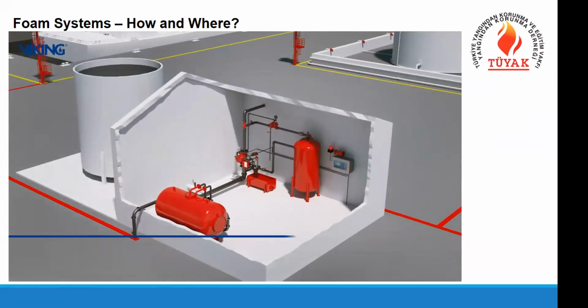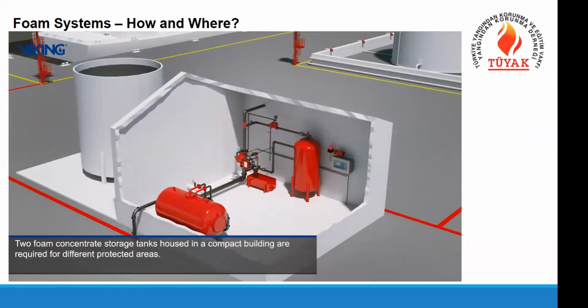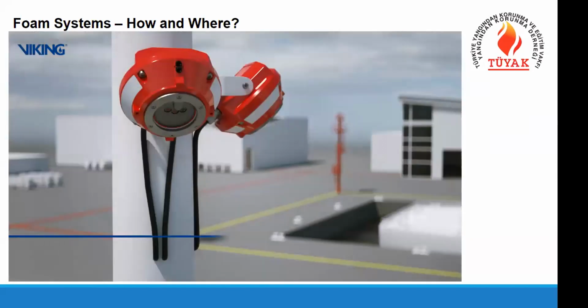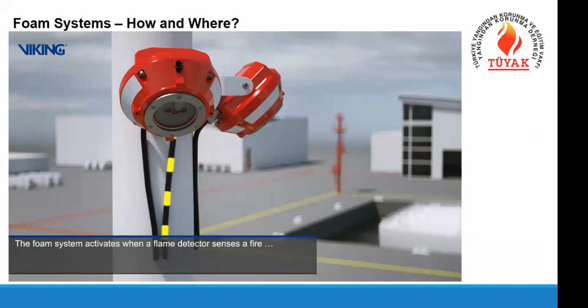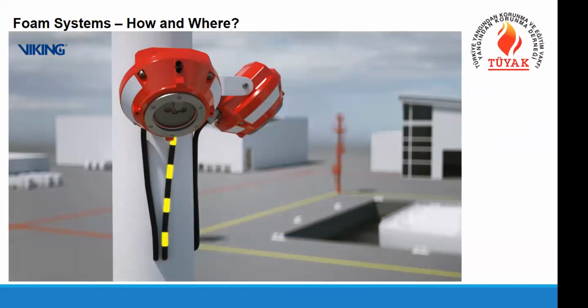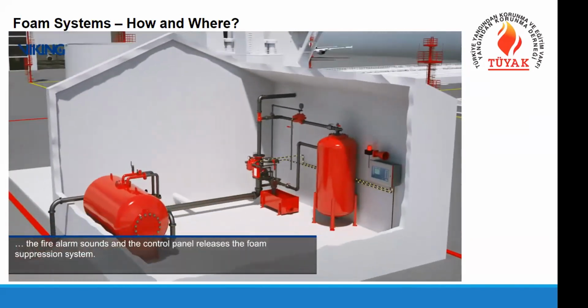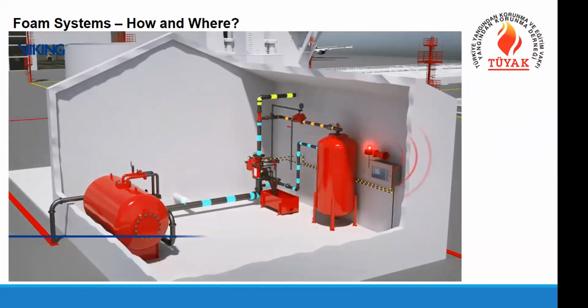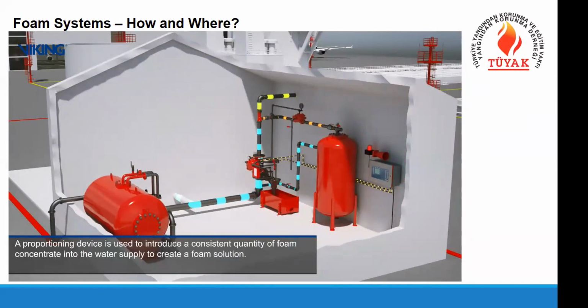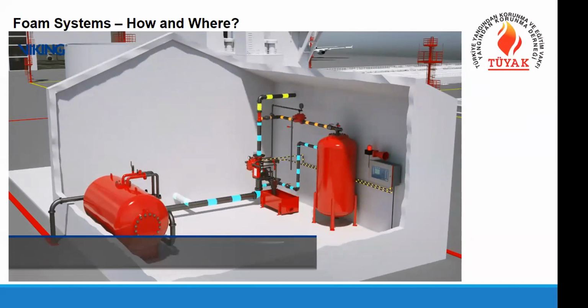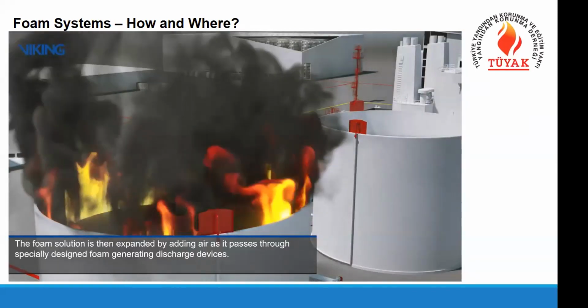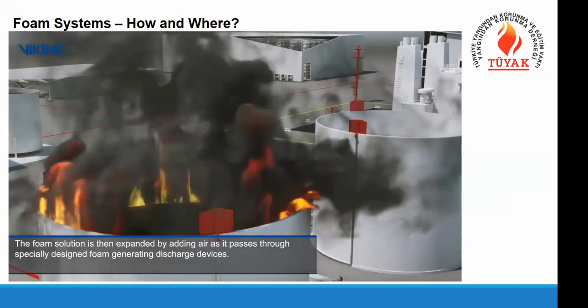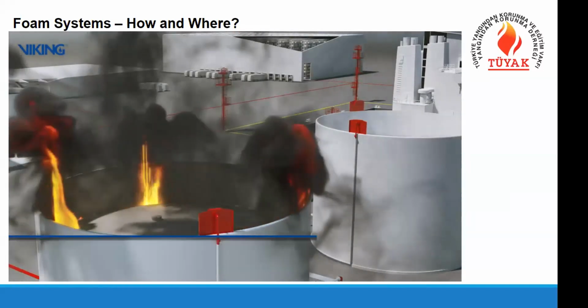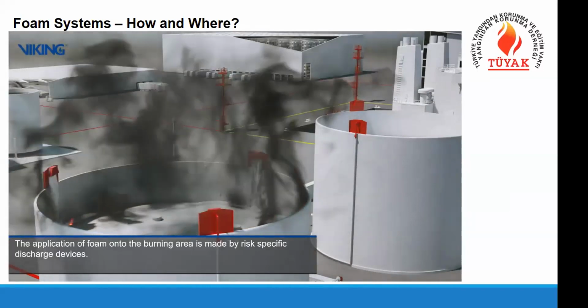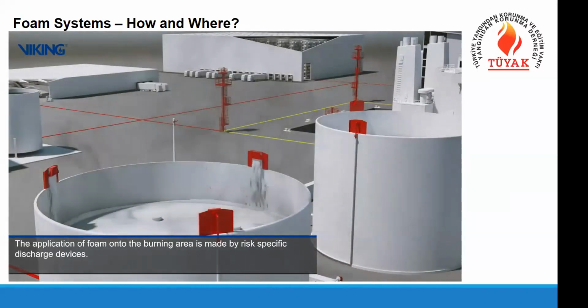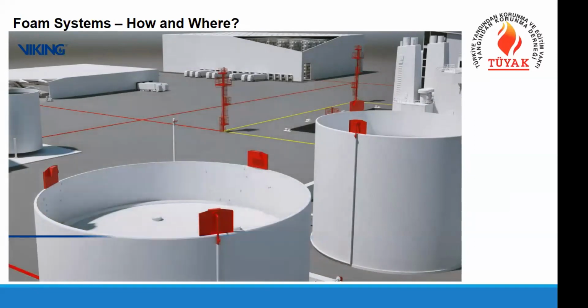We have foam tanks and a specialized center controlling the foam system. It works using detectors in the system, flame detectors or fire detectors, informing the system that we have a fire in the facility. In the related section, the deluge valve, as I showed you in previous slides, opens and sends water on the pipe from the proportioner. The proportioner mixes the foam in the necessary quantity and sends it out to the discharge devices over the tanks you see.